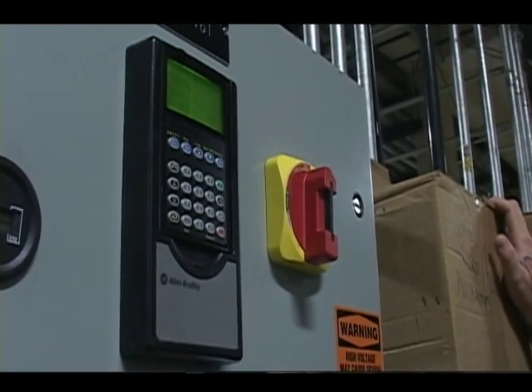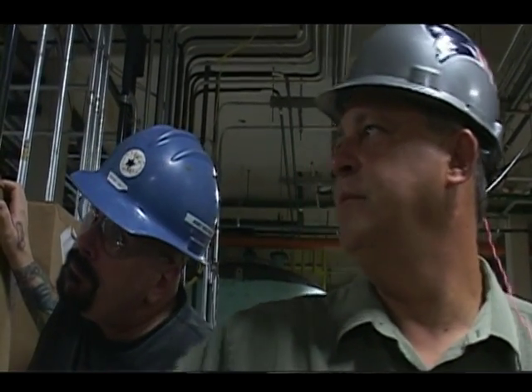And if you restart it, what's it look like? It'll come back to whatever it was last. Oh, okay. Oh, to keep it pretty steady. Yeah. As long as it's above 50. That is, however, programmable. Okay, the default in the drive basically is to go back to the last number. However, you can make it go to 0 if you want, but the default says go back to the last speed, whatever it was. Okay.